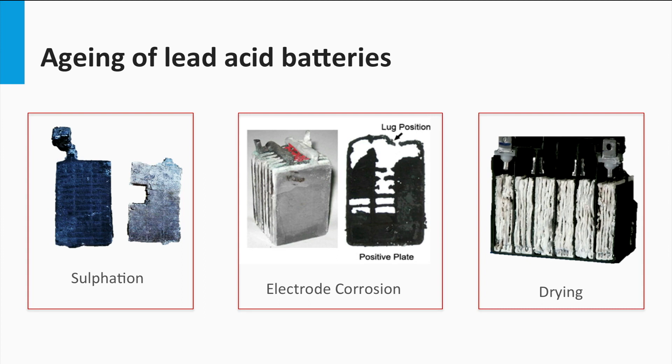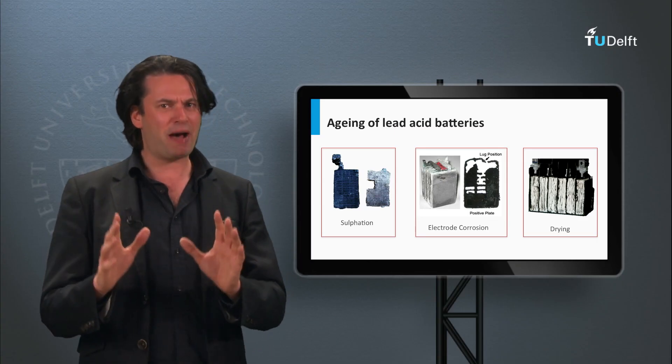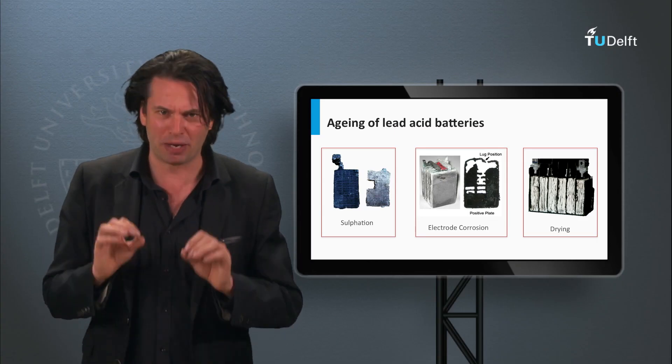Another cause is the drying out of electrolyte. Gassing can occur at high charging voltages resulting in loss of water. This should be replaced by timely addition of distilled water. Otherwise it dries out and the battery no longer functions. Thus the battery also suffers from a limited lifetime.